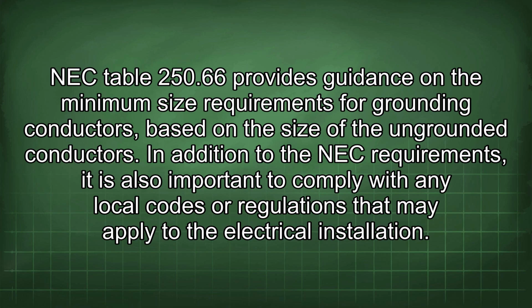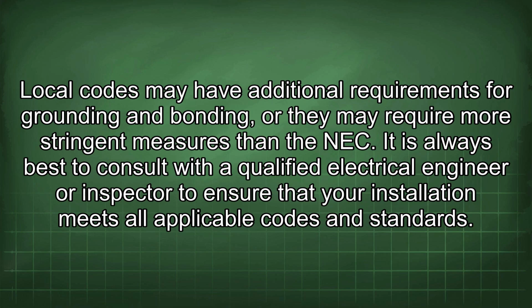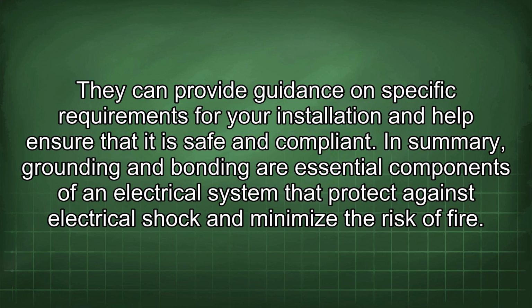NEC Table 250.66 provides guidance on the minimum size requirements for grounding conductors, based on the size of the ungrounded conductors. In addition to the NEC requirements, it is also important to comply with any local codes or regulations that may apply to the electrical installation. Local codes may have additional requirements for grounding and bonding, or they may require more stringent measures than the NEC. It is always best to consult with a qualified electrical engineer or inspector to ensure that your installation meets all applicable codes and standards. They can provide guidance on specific requirements for your installation and help ensure that it is safe and compliant. In summary, grounding and bonding are essential components of an electrical system that protect against electrical shock and minimize the risk of fire.